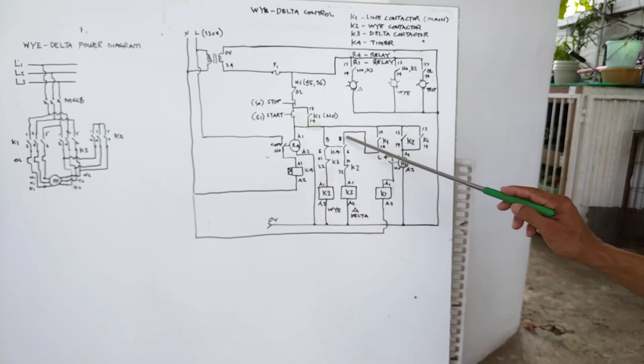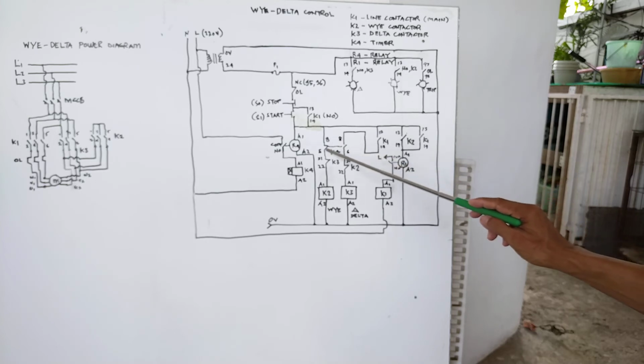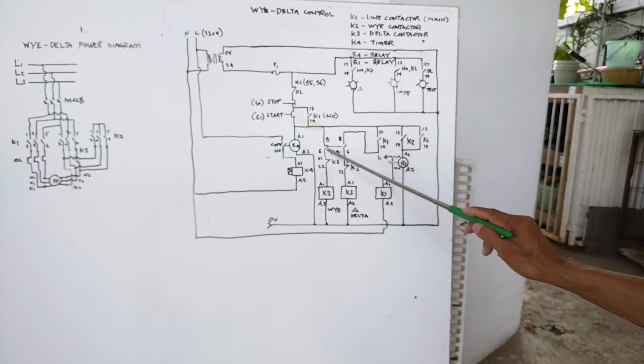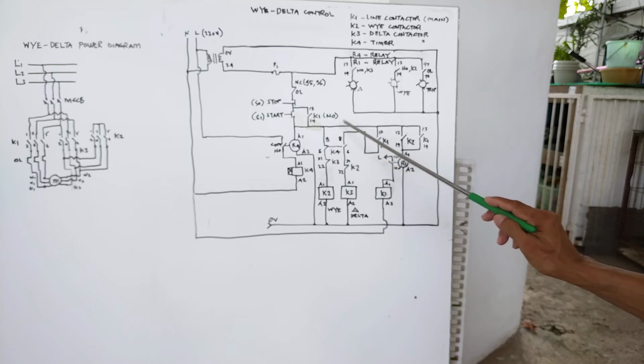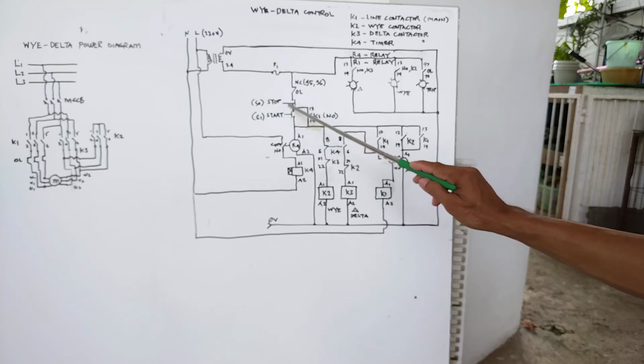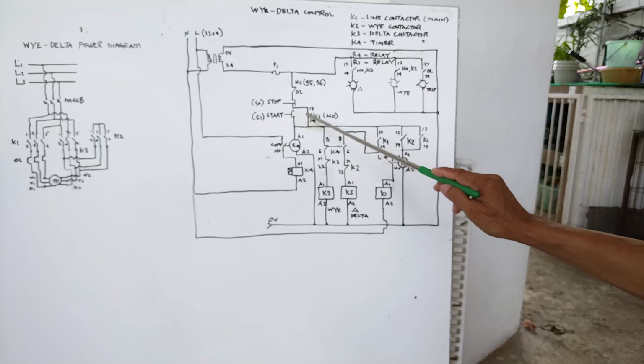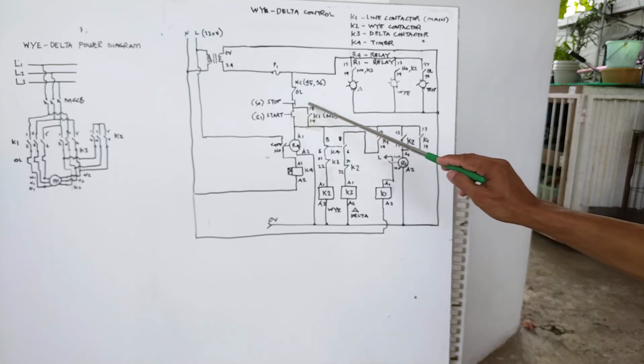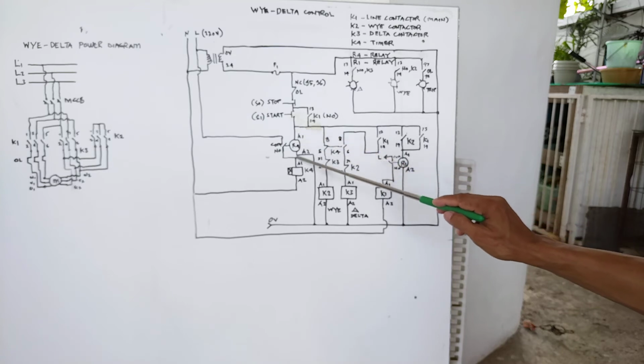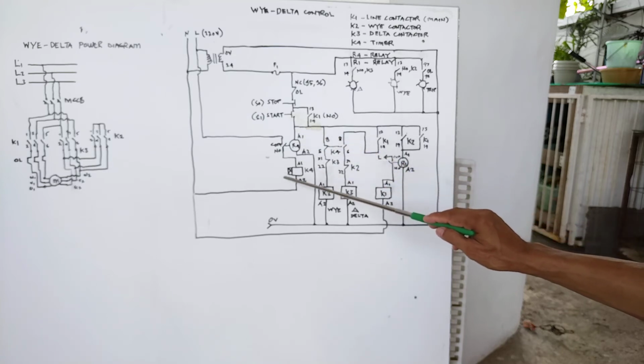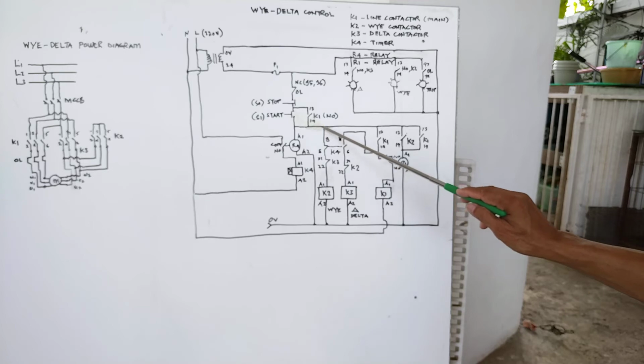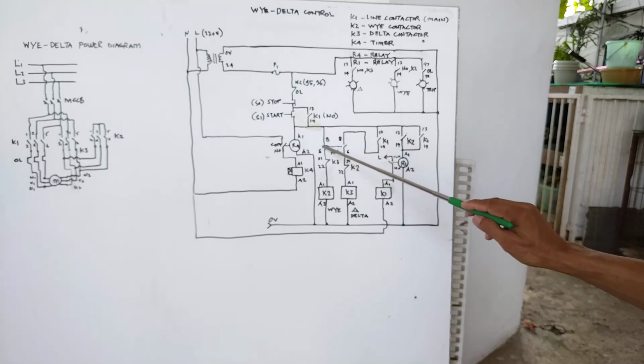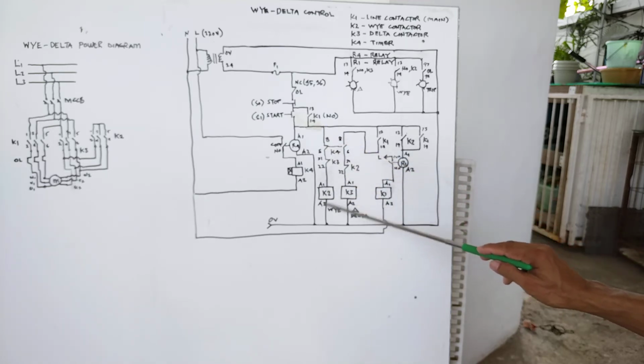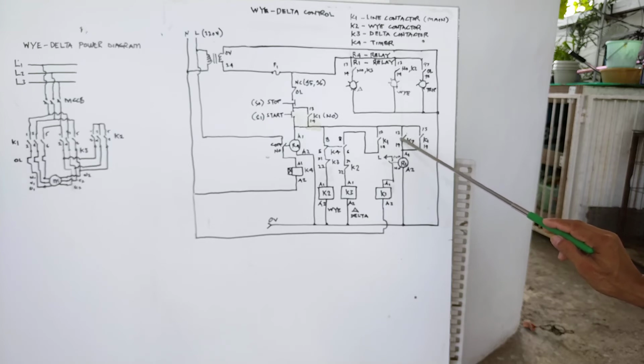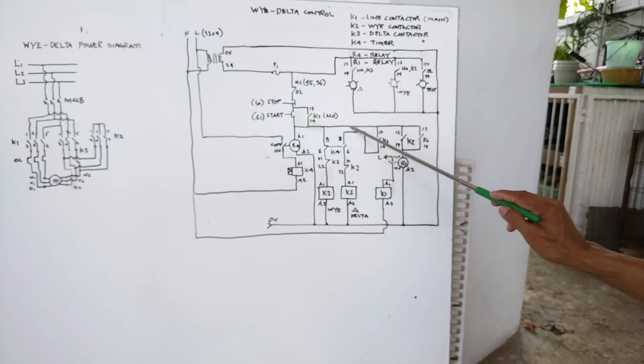Then after the time delay set in our timer, this normally closed contact will open, then this one will close. So when you release this, the 24 volts will be passing here. This one is what we call the latching contact. So 24 volts will pass here, then again come here, so this is again energized. Then this one, after the time delay, will open, then this one will be de-energized. This one will open.